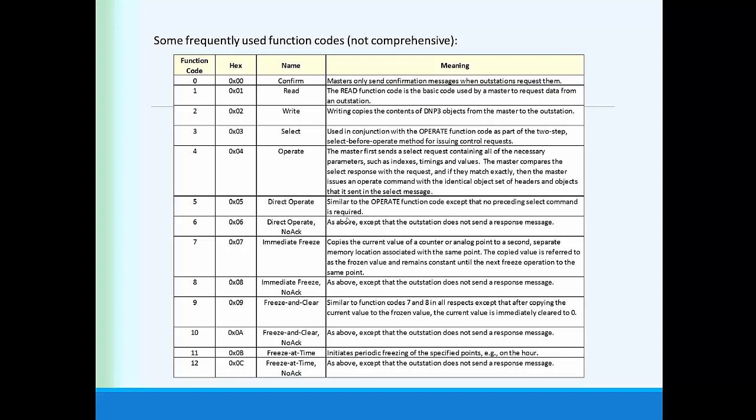So essentially, suppose you've got 200 meters that you want to read. And if you're using a serial protocol and you read meter number 1, and then a few milliseconds later you read meter number 2, and then a few milliseconds later you read meter number 3, by the time you've got to meter number 200, so much time has gone by, the kilowatt hours have continued to run, you don't have an idea of what the reading of the register was across the entire population at the same moment in time.